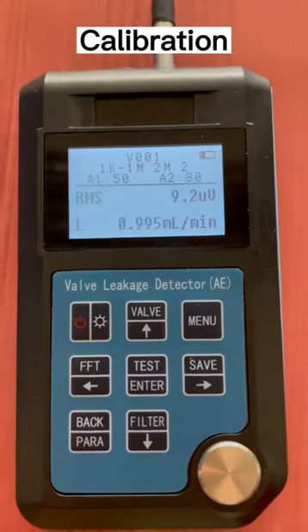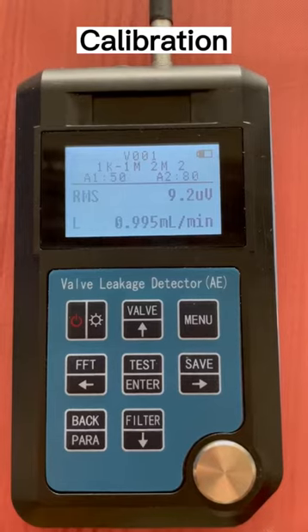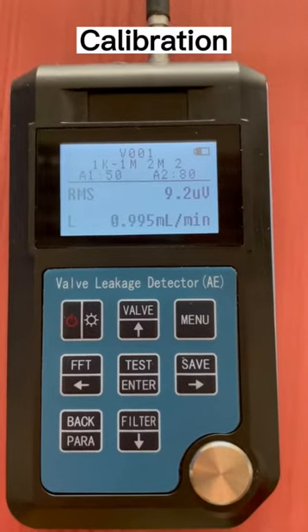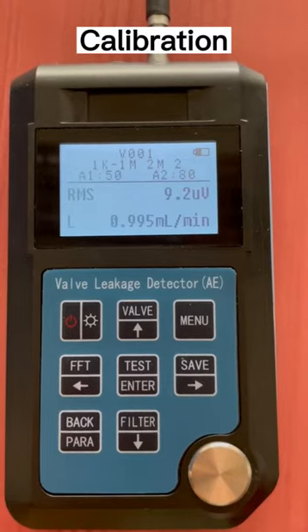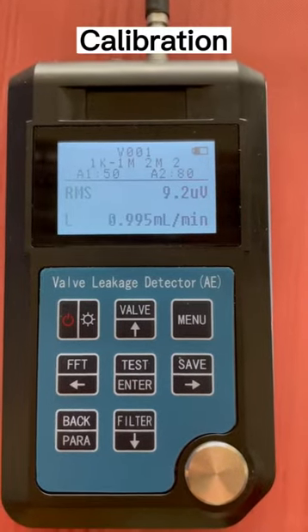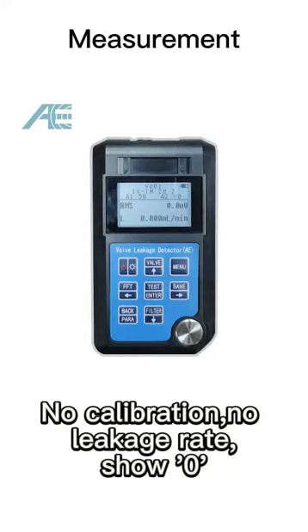Please note that there are a maximum of 8 calibration curves for each valve. The more calibrated points in the calibration curve, the more accurate the reference leakage rate that it can generate. Measurement. Whether the device has done the valve leakage calibrations or not, it can measure the valve leakages. The difference is, without calibration, there are only acoustic emission parameter values and the leakage reference rate is always 0. After calibration, it can show both acoustic emission parameters and the corresponding leakage reference rate.